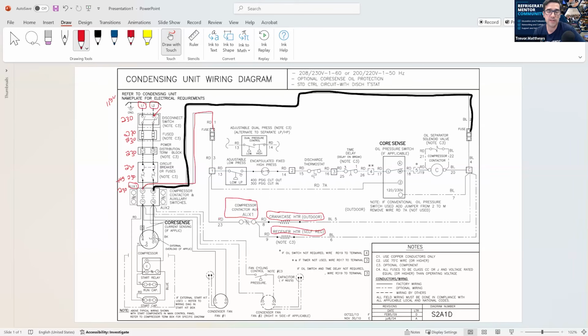Because that crankcase heater at this point, what we're looking at, that should be actually running, that crankcase heater, if we don't have this low pressure switch made. So how would we make that close? So what happens? Not on this drawing, on another page, I'm sure in the manual, it will show that you need a thermostat and a solenoid valve. And actually, when that thermostat makes, so the heat of the box or the heat of the walk-in starts to warm up, it will close that thermostat.